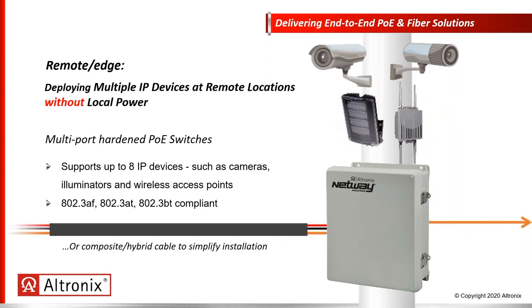Companies such as Belden, Superior Essex, and General Cable now provide standard offerings of composite fiber cable. Composite fiber, also known as powered fiber, is single mode or multi-mode fiber in the same jacket with copper wiring. This gives the ability to design a system based on the wattages required to deliver the necessary power. Generally, composite or hybrid powered fiber cable is available standard in 12 to 18 gauge, but every manufacturer mentioned will make custom cabling specific to your needs.